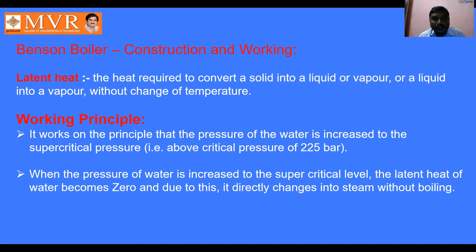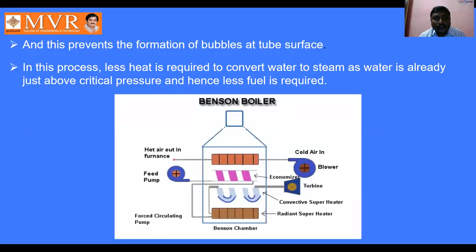Coming to the working principle of the Benson boiler: it works on the principle that the pressure of the water is increased to the supercritical pressure, that is above the critical pressure of 225 bar. When the pressure of water is increased to the supercritical level, the latent heat of water becomes zero, and due to this it directly changes into steam without boiling. This also prevents the formation of bubbles at the tube surface.